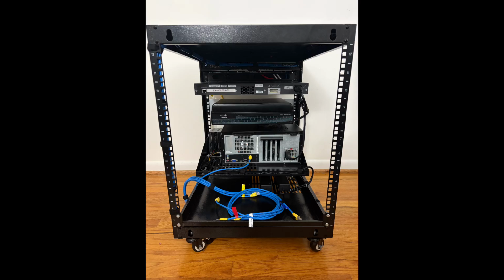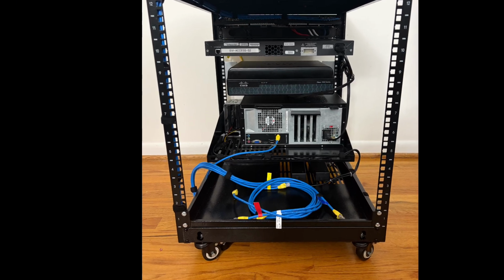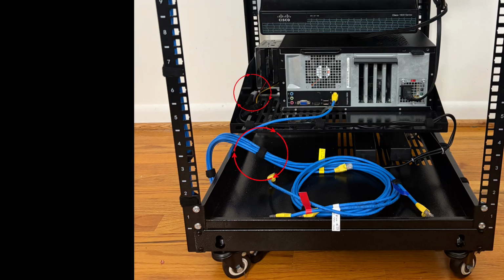Hands-on installation provides a better understanding of these physical characteristics than working with cables only in a diagram or simulation. The objective was to route the cables cleanly while avoiding unnecessary bends and maintaining an organized path through the rack. Velcro and plastic cable ties were used where appropriate to secure and organize the permanent cabling without placing excessive pressure on the cables.